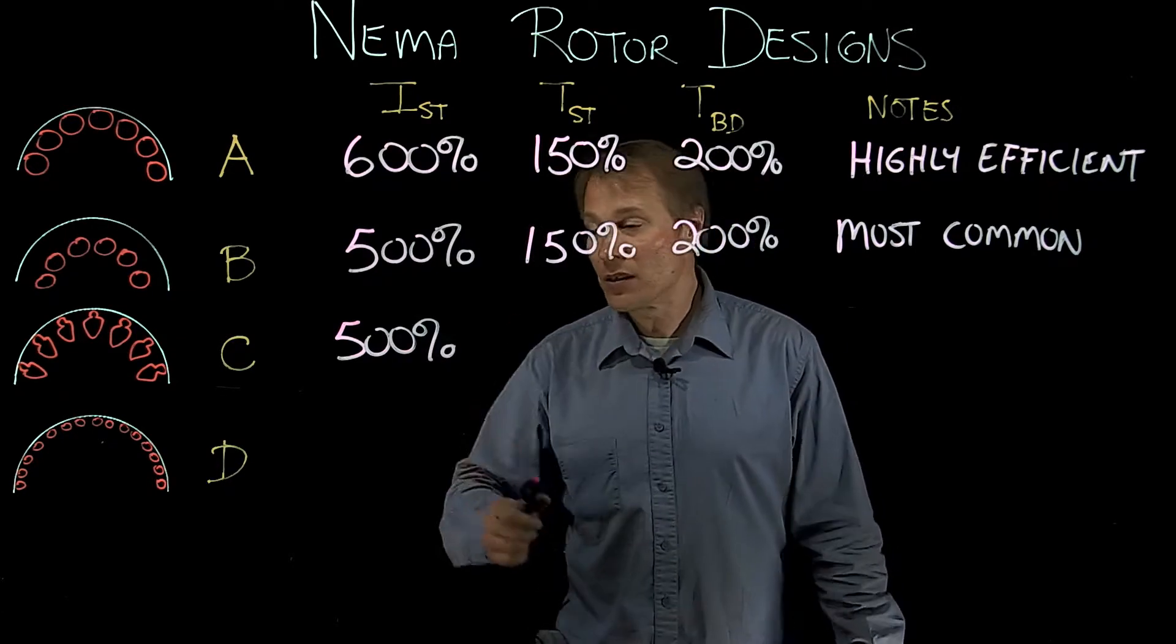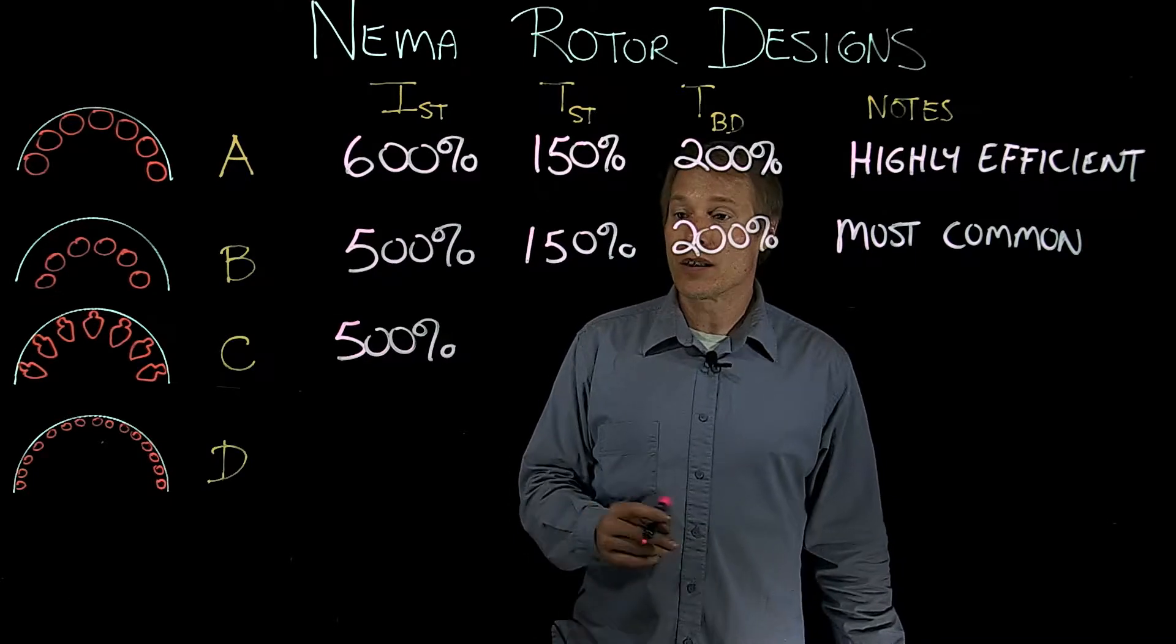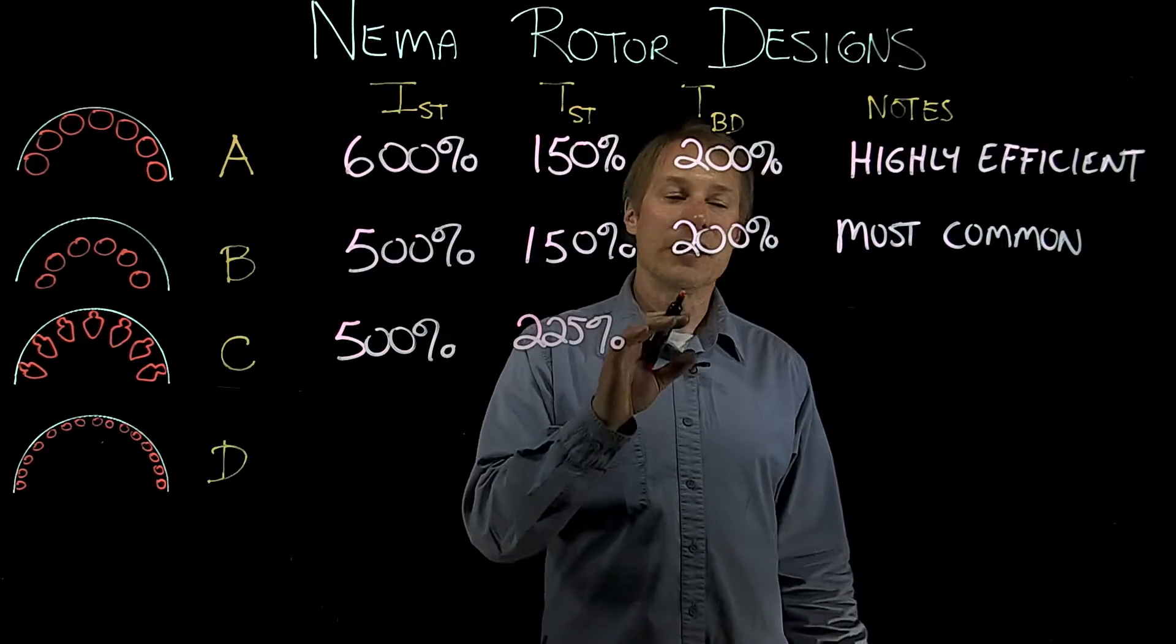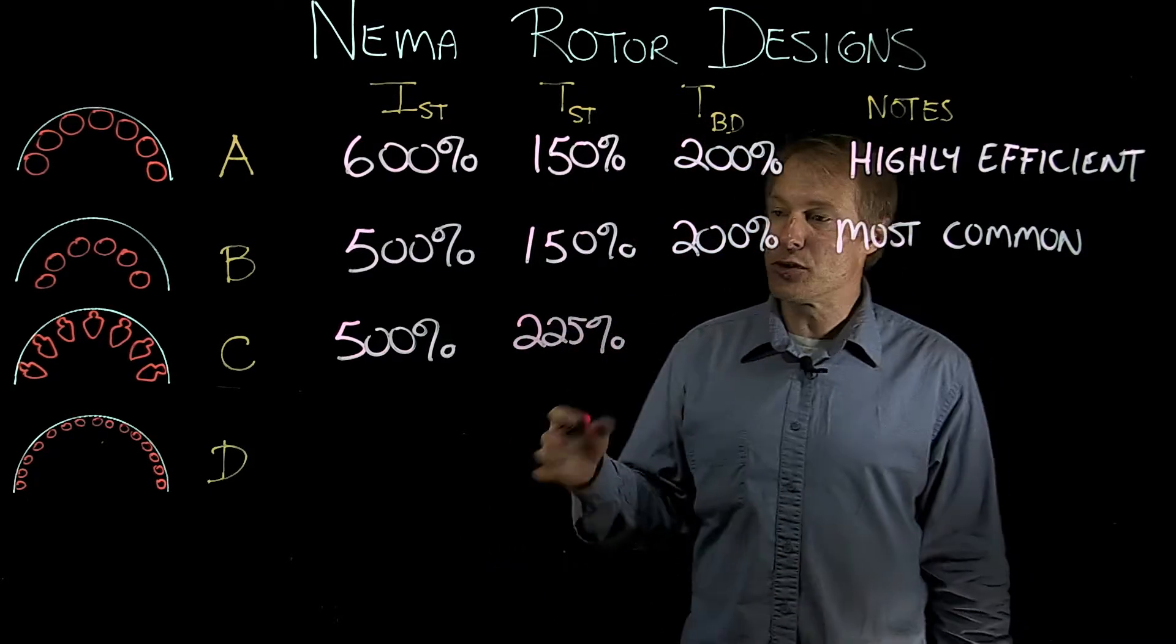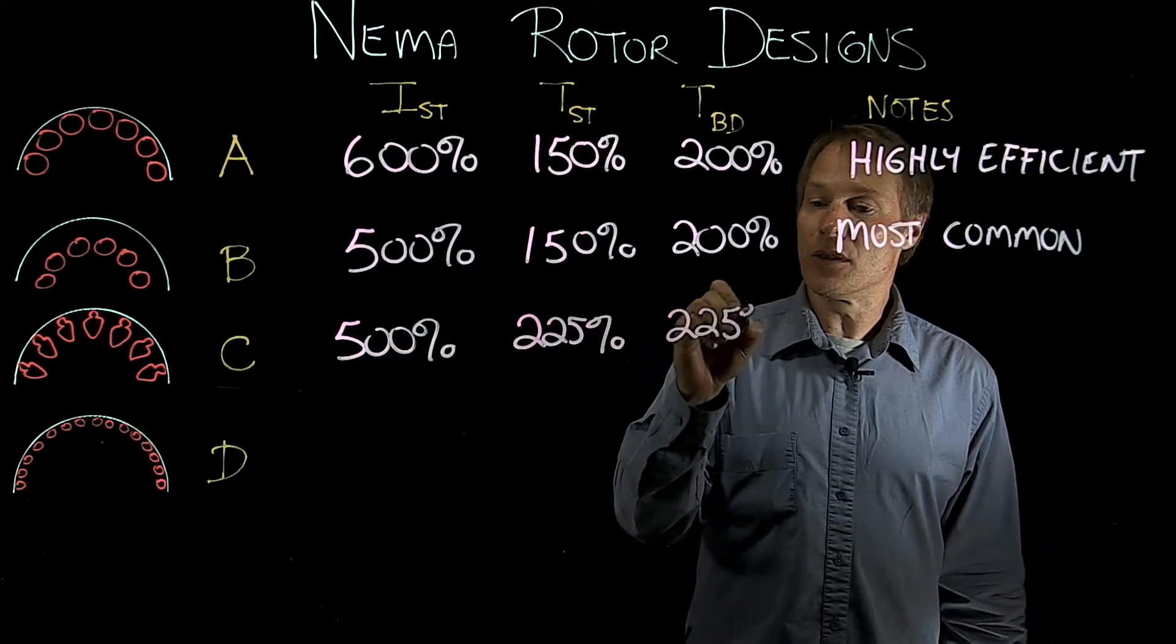So most of the current is going to go through the smaller rotor bars, in this case, or the edge ones, the outer edge ones. And that's going to raise the starting torque to 225%. Now the breakdown torque for a NEMA-C is usually right at start, so that will also be 225%.